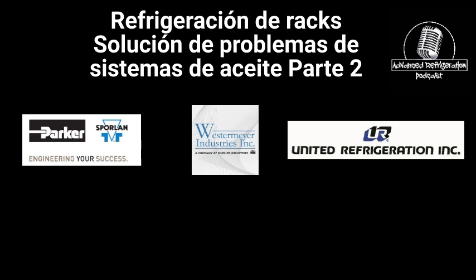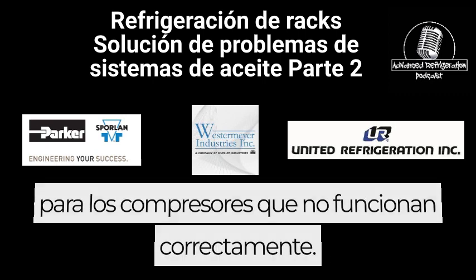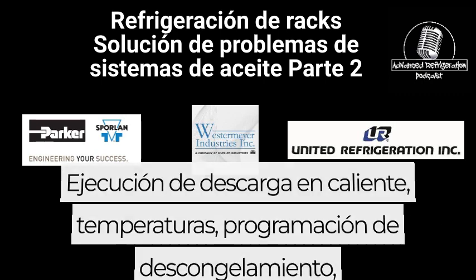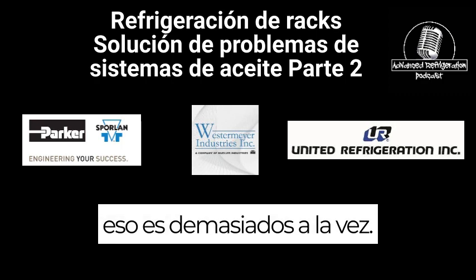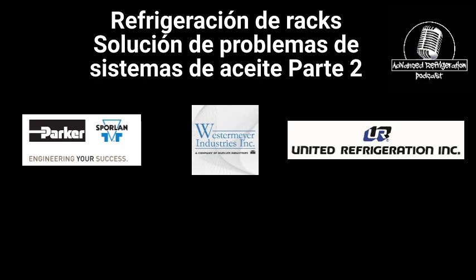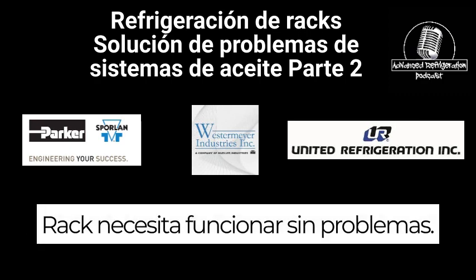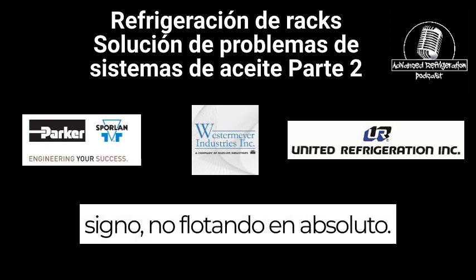So with high compressor cycles, you want to look out for compressors that are not operating properly, running high discharge temps, defrost scheduling that's too many at one time, overlapping hot gas defrost, stuff like that. That rack needs to run smoothly. Low suction pressure set lower than design, not floating at all.